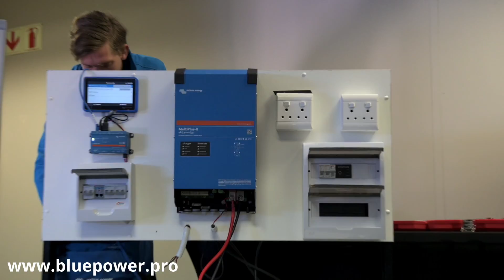For programming the Victron inverters, you require the Victron MK3 interface to USB, supplied by any Victron distributor. As an installer, you need one for each installation team, and it's required to update the firmware or settings on a Victron inverter, the MultiPlus or Quattro range. So to change settings or update firmware, we need the MK3 to USB device.